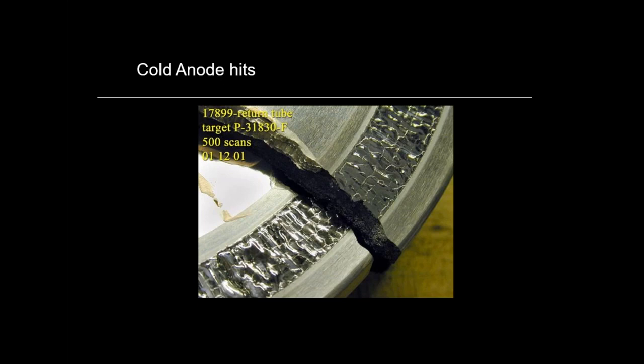The one you saw that went around has one spot in there. What's typically happening there is either the stator is dying, has a short, or the bearing's going. So the anode stopped and then kept going. As it stops, because it's getting so much energy, the target melted in that spot. A lot of times the manufacturer gets it back and says, check your stator drive, check your rotor board. That's what they're talking about, because they've seen that. And they'll say, you didn't calibrate the filament voltage. What they're looking at is whether the filament melted or whether it was a sharp crack. A sharp crack means it was a material failure. If it melted, that means it was too much voltage.